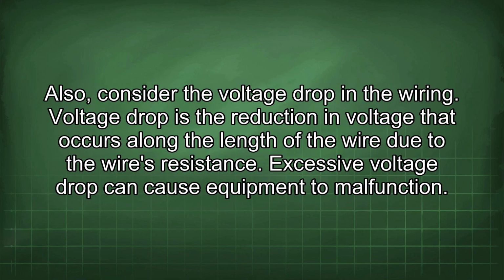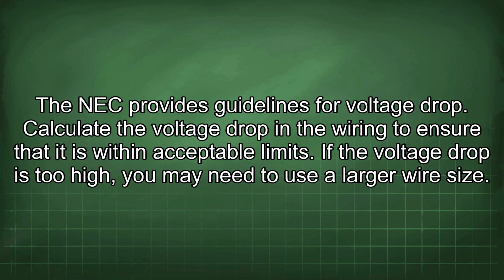Also, consider the voltage drop in the wiring. Voltage drop is the reduction in voltage that occurs along the length of the wire due to the wire's resistance. Excessive voltage drop can cause equipment to malfunction. The NEC provides guidelines for voltage drop. Calculate the voltage drop in the wiring to ensure that it is within acceptable limits. If the voltage drop is too high, you may need to use a larger wire size.